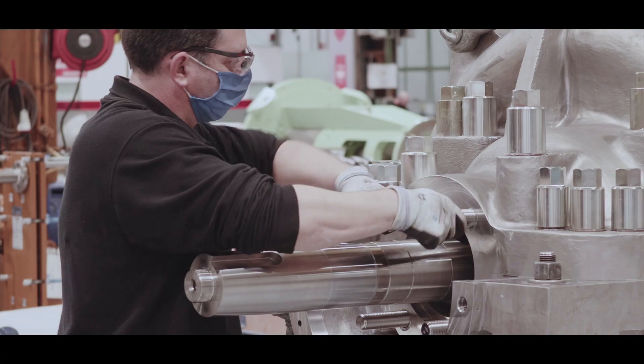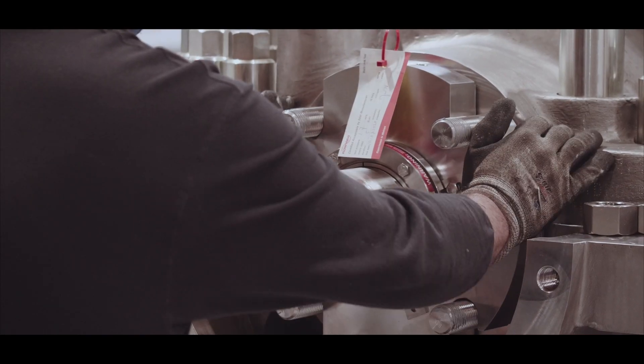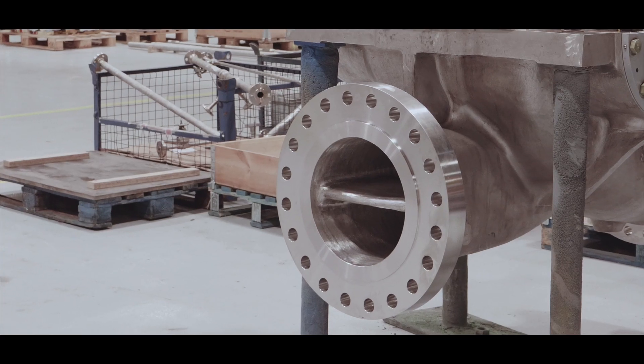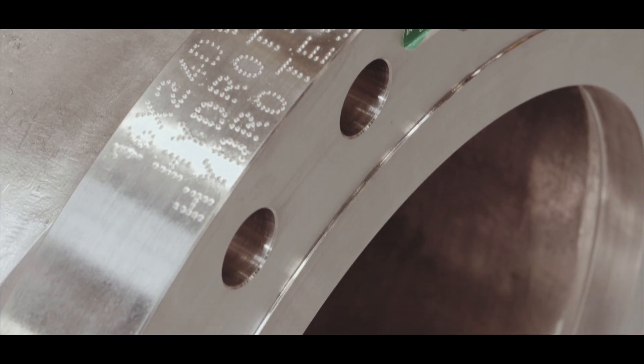Generously sized seal chambers for optimal flushing and cooling accept single cartridge type mechanical seals as well as double or tandem cartridge type designs. The suction and discharge nozzles are cast in the lower casing to permit pump disassembly without disturbing the piping.